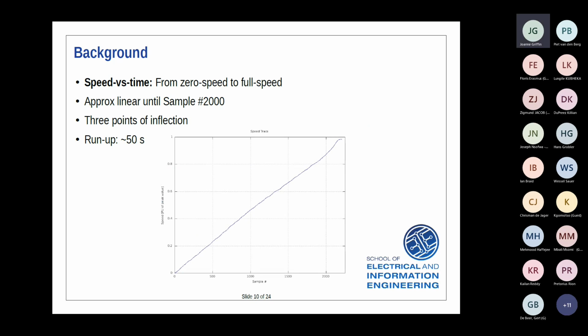Okay, so just to continue, we use our handheld tachometer. The scales are a bit small here, I apologize. The y-axis is the speed in per unit from standstill to full speed. And the x-axis, in this case, is the number of samples, but you can think of that as time. And in fact, for this particular machine, I think the run-up time is about 50 seconds. The x-axis from the left to the right is about 50 seconds. I can't remember exactly what the rated speed of this machine was, but I think you can all immediately see that it's pretty straight. The line is pretty straight.